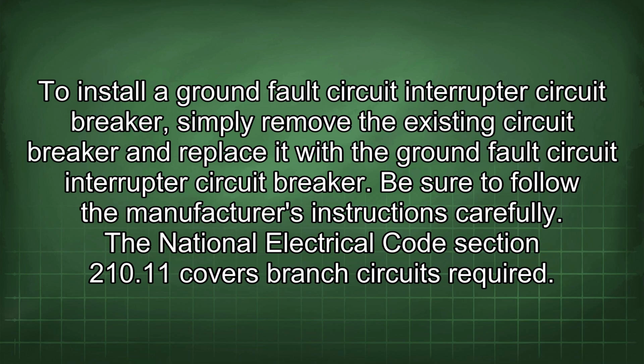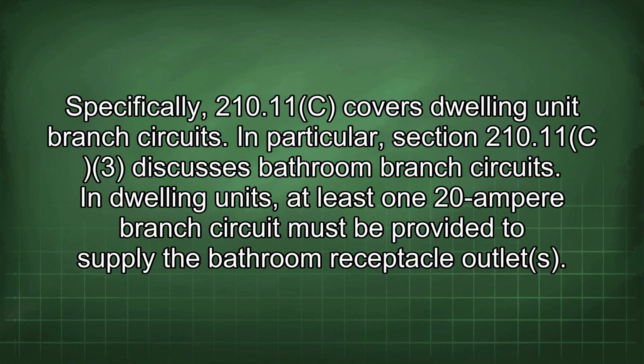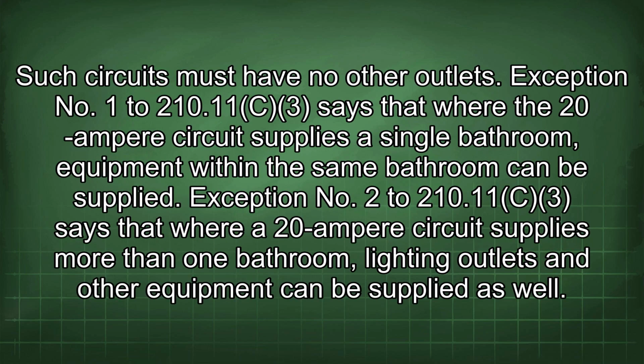The National Electrical Code Section 210.11 covers branch circuits required. Specifically, 210.11c covers dwelling unit branch circuits. In particular, Section 210.11c3 discusses bathroom branch circuits. In dwelling units, at least one 20 ampere branch circuit must be provided to supply the bathroom receptacle outlets. Such circuits must have no other outlets. Exception No. 1 to 210.11c3 says that where the 20 ampere circuit supplies a single bathroom, equipment within the same bathroom can be supplied.